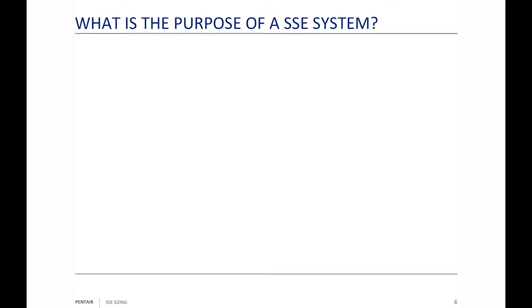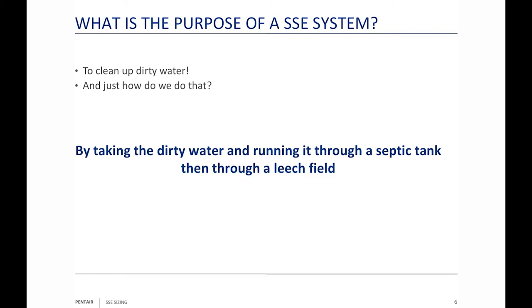What's the purpose of an SSE system? It's to clean up dirty water — by taking the dirty water and running it through the septic tank and then through a leach field. It's going to come out of the house into a septic tank. Remember, every gallon in pushes a gallon out. You could have a gravity feed system, pushing it right into the leach field, or a pumping chamber that turns on when it has the correct amount of water.